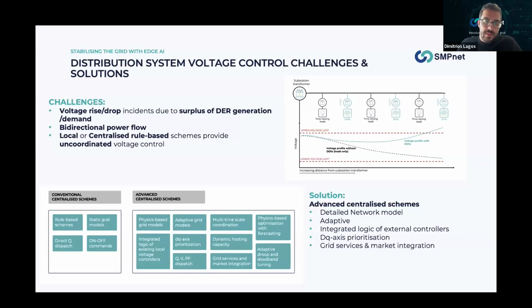And to do that, this centralized scheme has to have a detailed network model, which means that it has a physics-based grid model with all the electrical characteristics of the network and the physical equations to model accurately the impact of the different resources. It has to be adaptive, so of course, this network model has to be updated with the latest status of breakers in the network to have the actual active topology, and the latest measurements and forecasts to provide the optimal actions for the DERs.